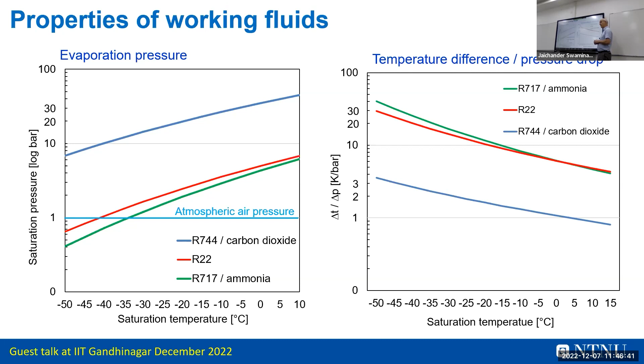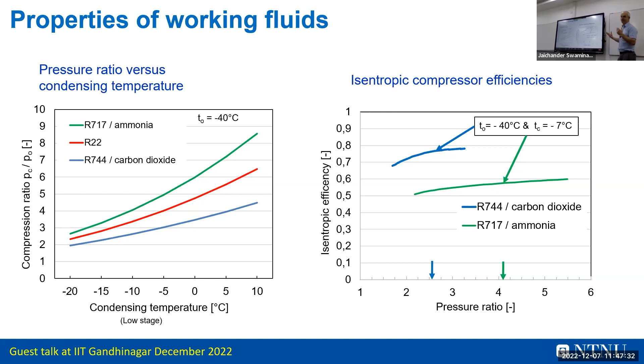That helps. Another thing is the pressure ratio versus condensing temperature. And here you see low values. For CO2, the pressure ratio, that's what matters for the compressor. I mean, it's not the absolute pressure, it's the ratio between suction and discharge. And there we have relatively low numbers for CO2, which means you can have a very high isentropic efficiency compared to other fluids, which need a larger ratio to do the same duty, and then you're at lower values. So these are all the details. If you do just some simple analysis and you just assume it's always the same, the results are not the same. But here comes your diagram.